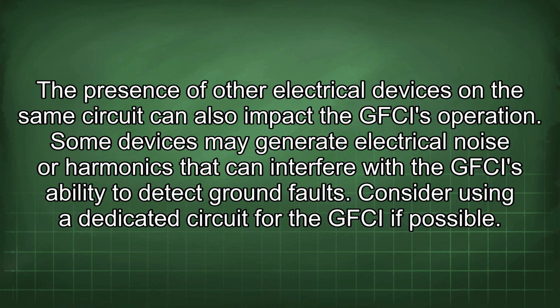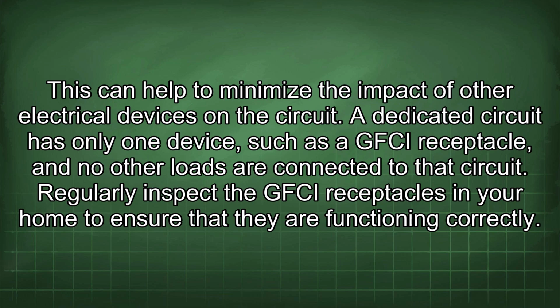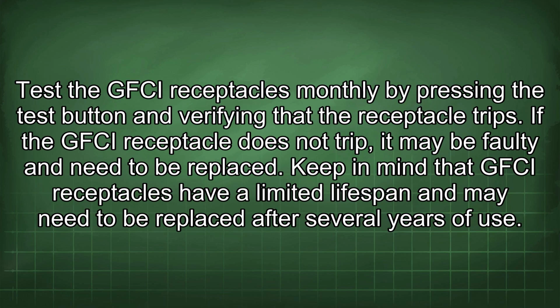Consider using a dedicated circuit for the GFCI if possible. This can help to minimize the impact of other electrical devices on the circuit. A dedicated circuit has only one device, such as a GFCI receptacle, and no other loads are connected to that circuit. Regularly inspect the GFCI receptacles in your home to ensure that they are functioning correctly. Test the GFCI receptacles monthly by pressing the test button and verifying that the receptacle trips. If the GFCI receptacle does not trip, it may be faulty and need to be replaced.